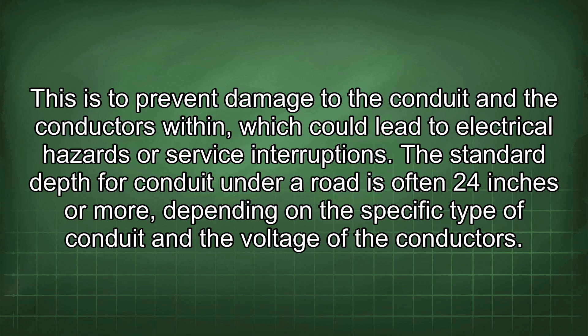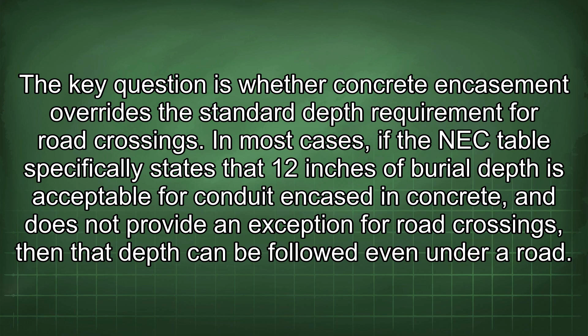The key question is whether concrete encasement overrides the standard depth requirement for road crossings. In most cases, if the NEC table specifically states that 12 inches of burial depth is acceptable for conduit encased in concrete and does not provide an exception for road crossings, then that depth can be followed even under a road. However, this is contingent on strict adherence to the concrete encasement specifications, such as the thickness of the concrete and the type of concrete used.